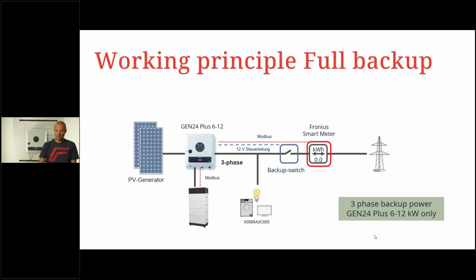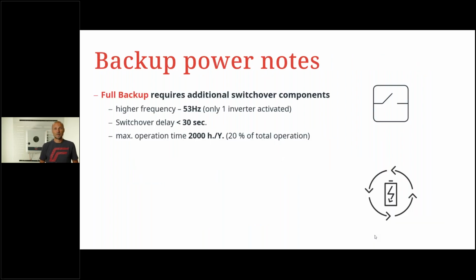I'll now continue in my presentation, and now some notes about backup power. What do you need to know? Basically, full backup requires additional components. I already told you that: switchover components, contactor, the relay. Second, we have a higher frequency in full backup power mode with 53 Hertz. We supply all the loads, but all additional solar inverters will be kicked out. So we have only one inverter running in backup power mode. That's important. Third, there is a short switchover time of up to 30 seconds. We will reduce that. I'll come back with detailed information about that at the end of the presentation.